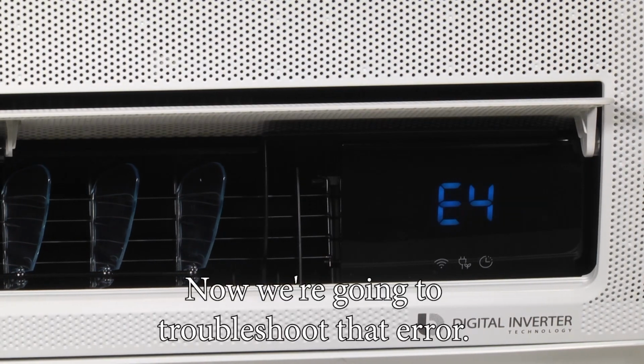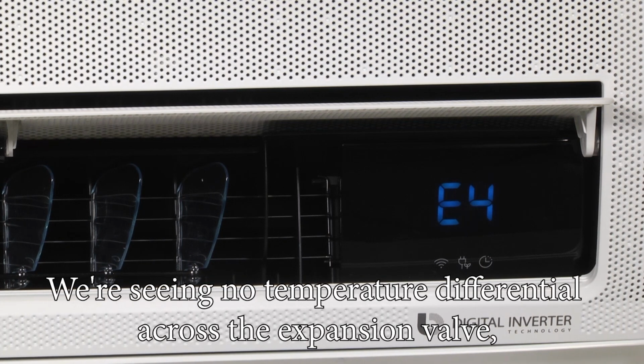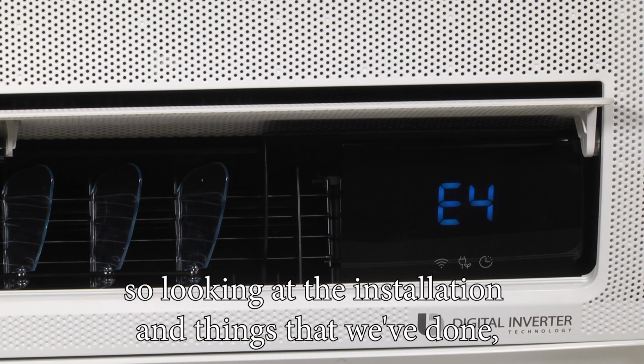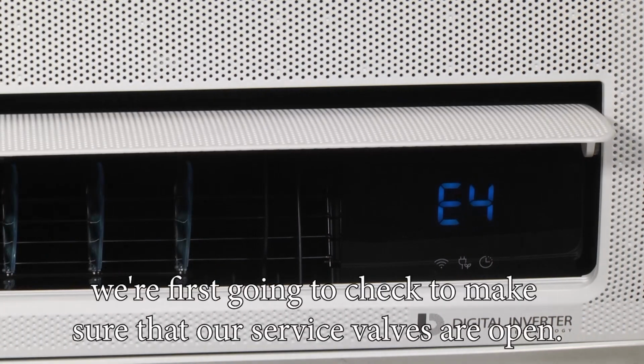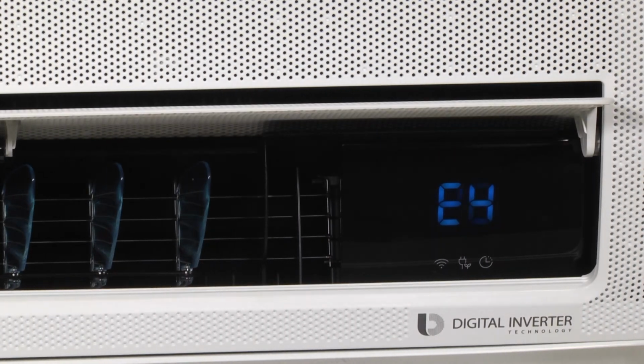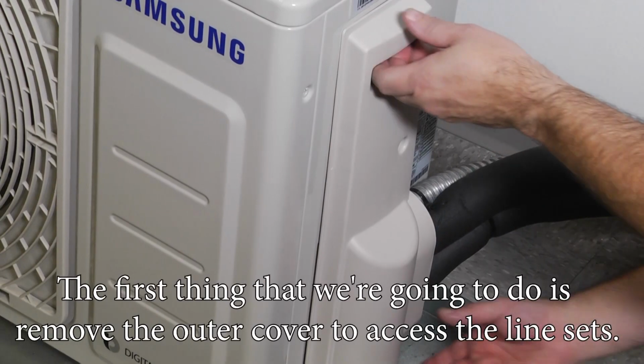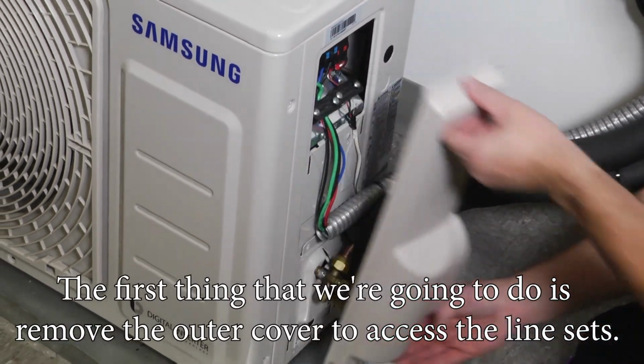So now we're going to troubleshoot that error. Basically, we're seeing no temperature differential across the expansion valve. Looking at the installation steps we've done, we're going to first check to make sure our service valves are open. So the first thing we're going to do is remove the outer cover to access the line sets.